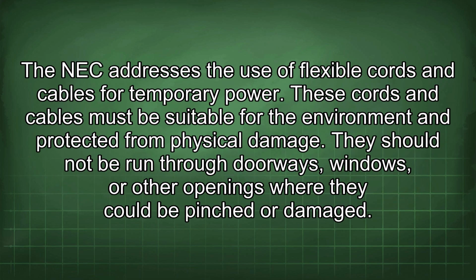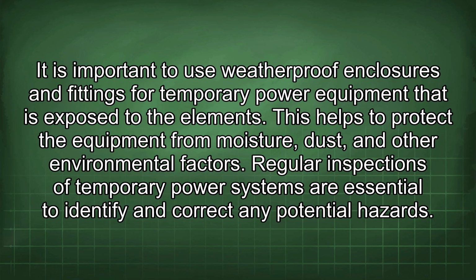The NEC addresses the use of flexible cords and cables for temporary power. These cords and cables must be suitable for the environment and protected from physical damage. They should not be run through doorways, windows, or other openings where they could be pinched or damaged. It is important to use weatherproof enclosures and fittings for temporary power equipment that is exposed to the elements. This helps to protect the equipment from moisture, dust, and other environmental factors.